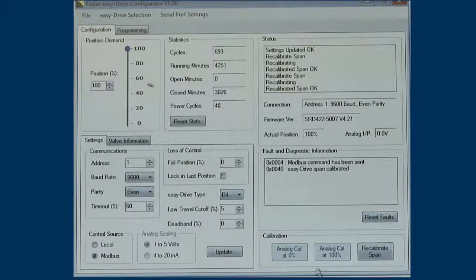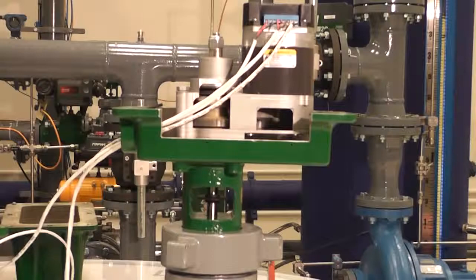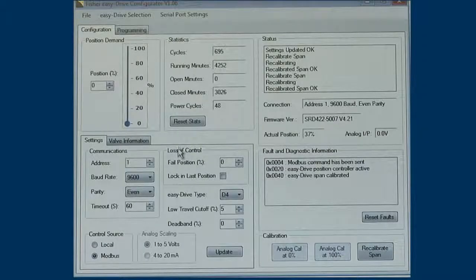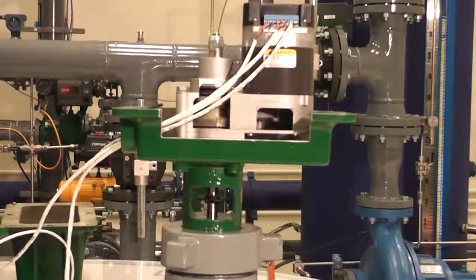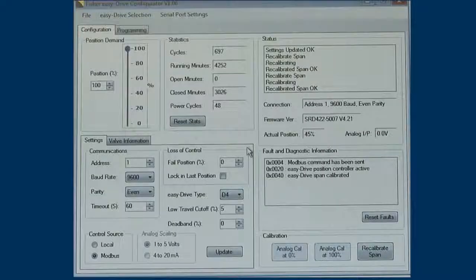After the unit has finished the calibration cycle, use the position demand in the upper left-hand corner and slide the dot all the way to the bottom. The valve should move to the closed position. Make sure that within the status bar, the actual position is listed as 0% travel. Now slide the dot to the top of the position demand and the valve should move to fully open. Make sure the actual position within the status bar reads 100% travel. If the purpose was to operate the valve using a Modbus control signal, you have finished calibration.